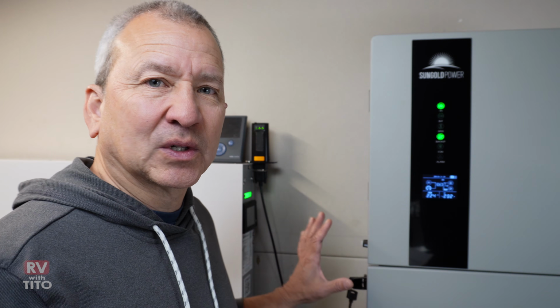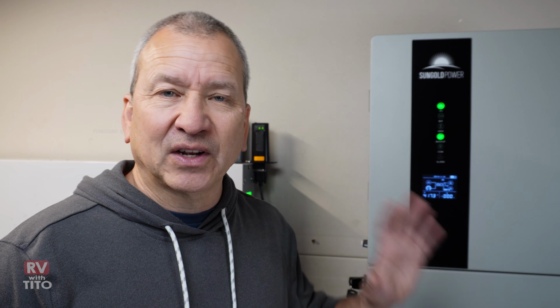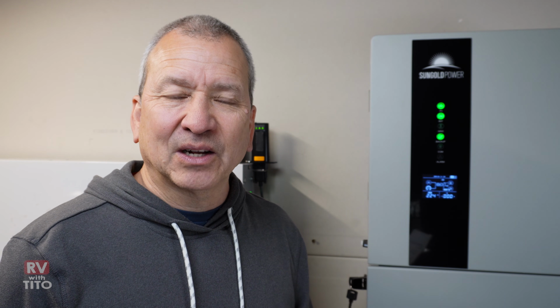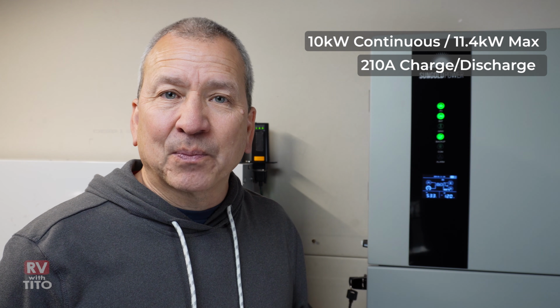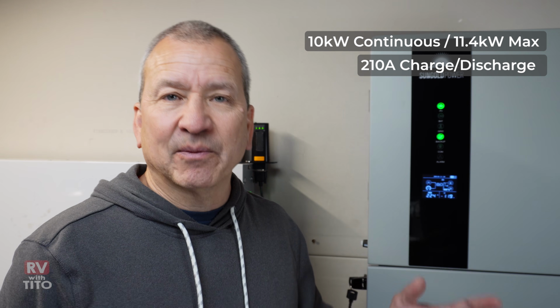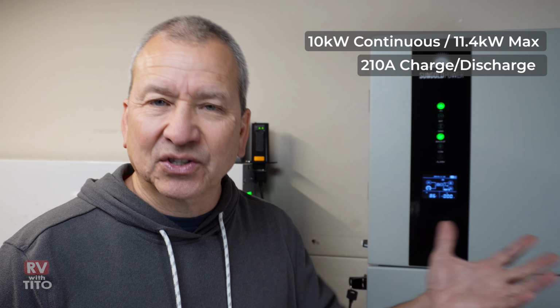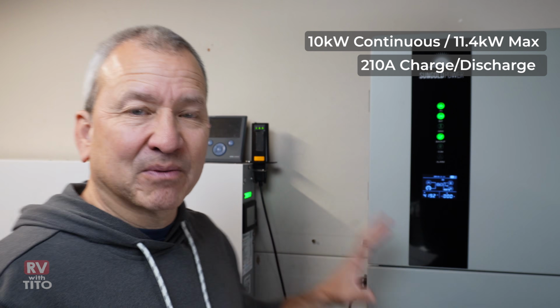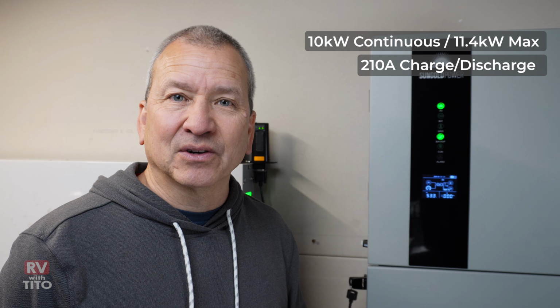So this is a 48 volt inverter, so it takes a 48 volt DC battery source, lithium iron phosphate or even lead acid. I'll show you how I have mine set up. It also has a 10 kilowatt continuous output, a 210 amp charge and discharge limit, and a maximum of 400 amps for about 1 second. So if you have any surges or big inductive loads that fire up, make sure your batteries can support it, and the inverter should be just fine.